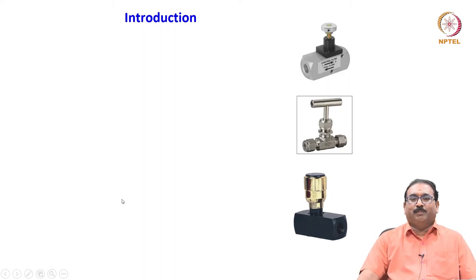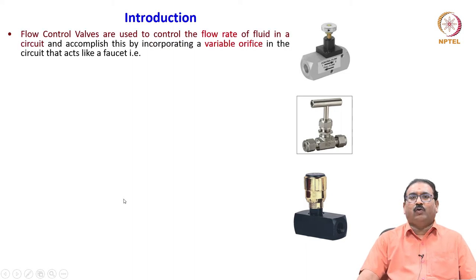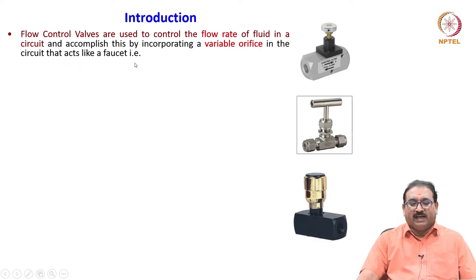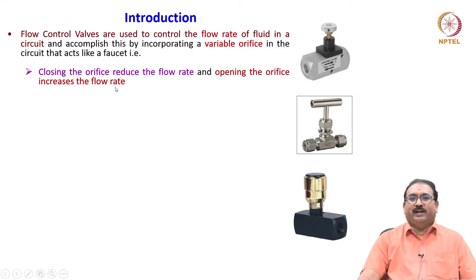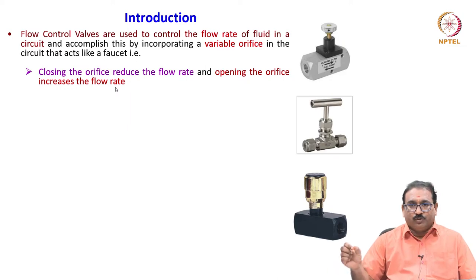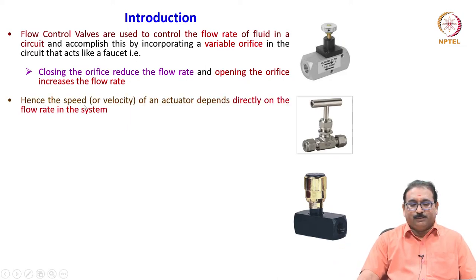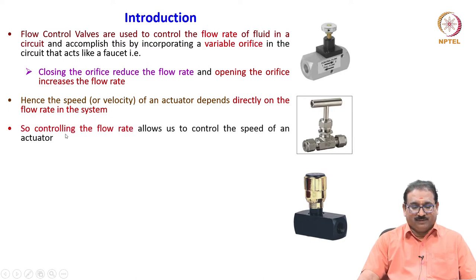I will give you a brief introduction about the flow control valve. Flow control valves are used to control the flow rate of a fluid in a circuit, accomplished by incorporating a variable orifice that acts like a faucet — closing the orifice reduces the flow rate and opening it increases the flow rate, like a tap in your bathroom. Hence, the speed or velocity of an actuator depends directly on the flow rate in the system, so controlling the flow rate allows us to control the speed of an actuator.